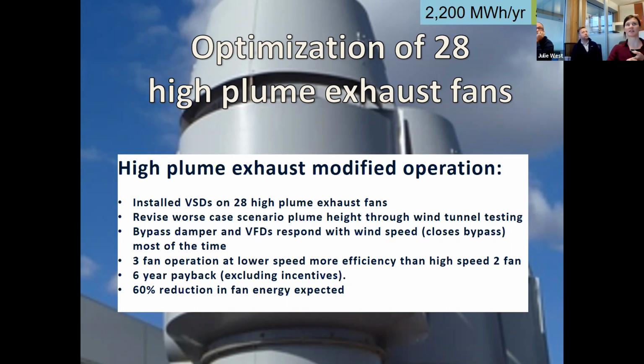The other thing we did is that only 2 of the 3 fans on the stack were operating before, and it's actually more efficient for fans to operate at a lower speed. So if you run all 3 fans rather than just 2 of them, you can increase the efficiency of the motor. And these 2 measures combined resulted in a 60% reduction in fan energy, a 6-year payback, and roughly 5% saving in building energy use.